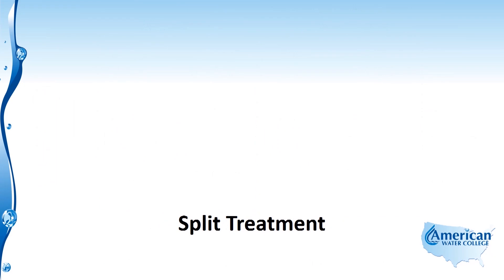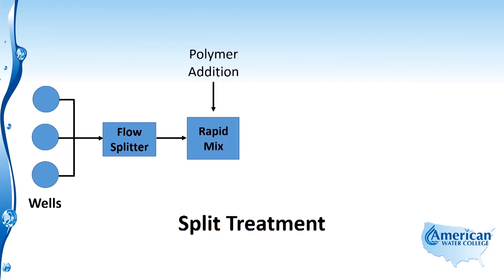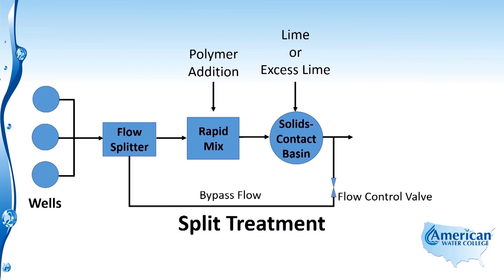The last method is called split treatment, a variation of the softening process intended to reduce chemical usage by splitting the flow stream. Hard groundwater from wells flows into a flow splitter, where it goes one of two places: into the rapid mix where polymer or coagulant is added, then into a solids contact basin where lime or excess lime is added; or bypassed through a flow control valve, skipping the rapid mix and solids contact basin entirely. This allows only a portion of the water to be treated, while the bypassed flow maintains its hardness and alkalinity.